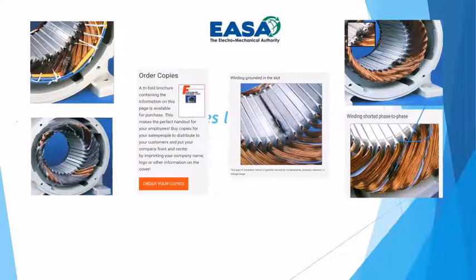Like here, this ended up being a surge. The surge from those coil connections fed into the motor with a high impedance. This is inductance, so it wants to resist it and tries to hold it, and that surge raises the instantaneous voltage and actually shorts the coil out. Normally you'll see that from some of the spiking that goes on. This one is showing phase loss, which is when the motor was single phased. This shows one section of the windings. Again, this is a 4-pole machine: 1, 2, 3, and 4.